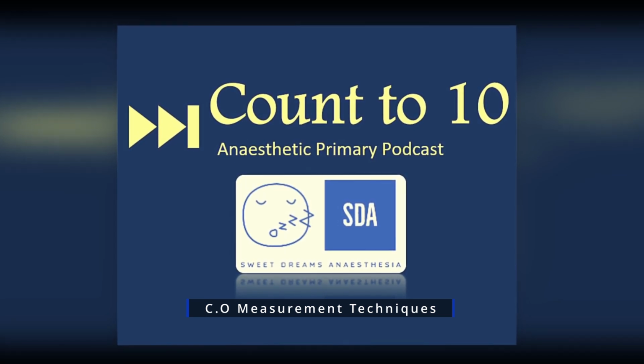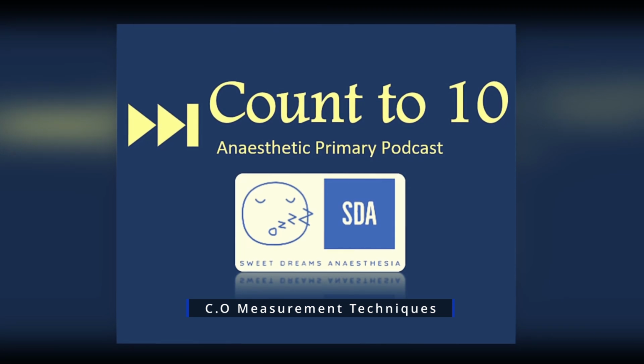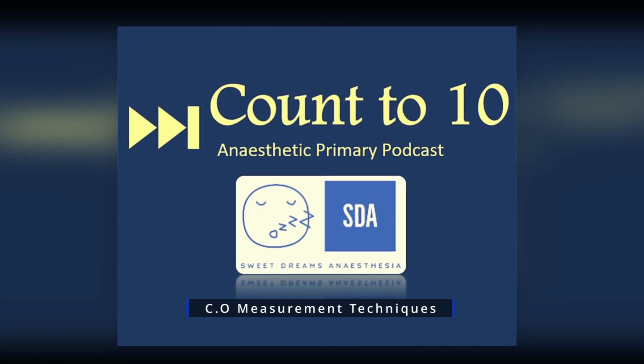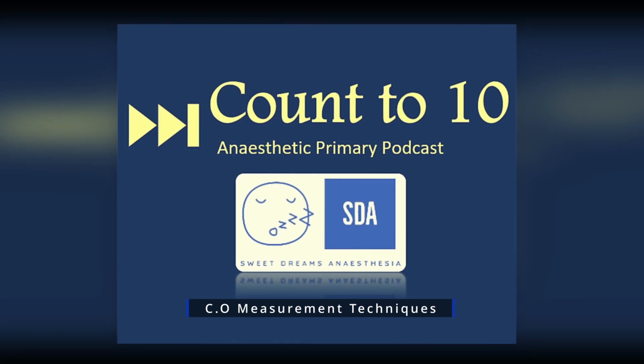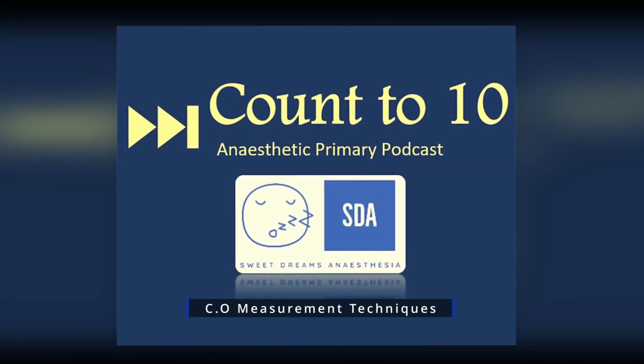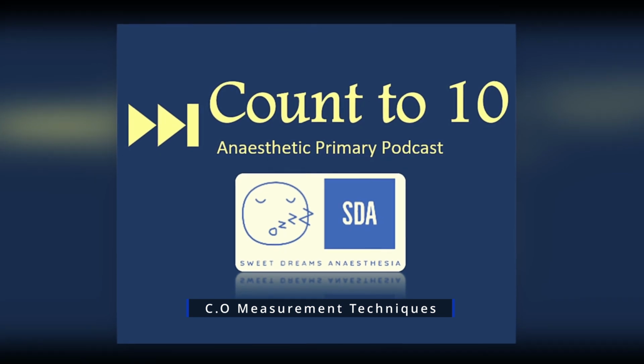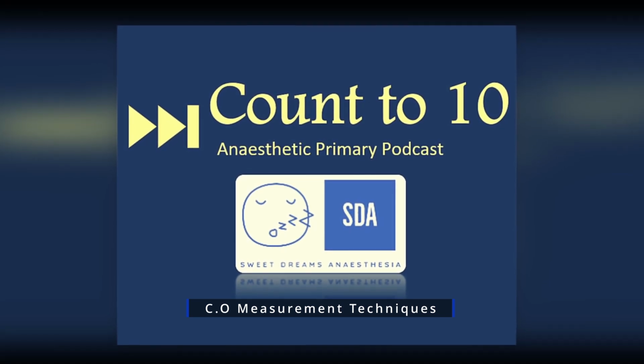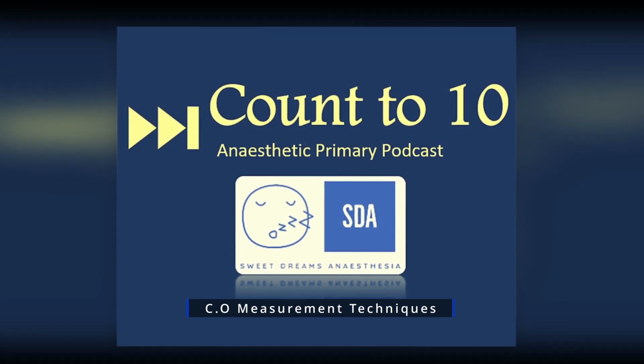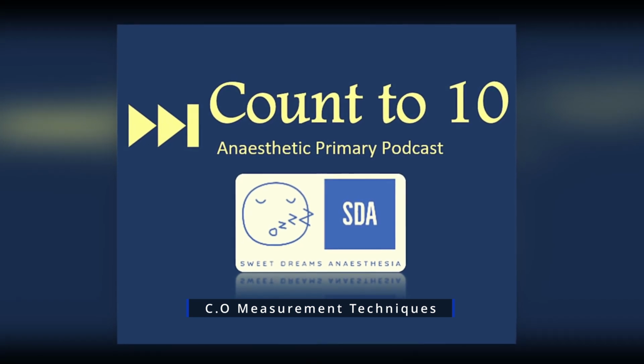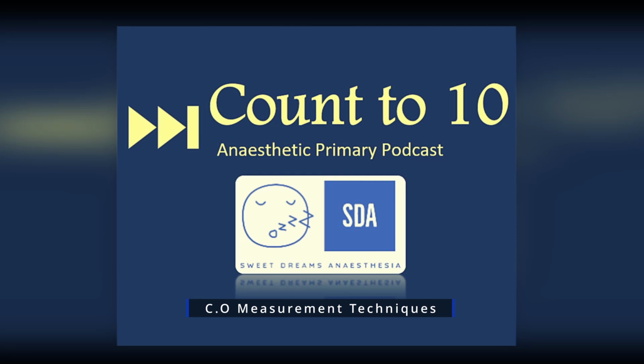Now these measurements are put into a complex equation called the Stewart-Hamilton equation, which describes this relationship and then spits out a cardiac output. The key thing with this technique is that you shouldn't just do it once. You should do this measurement 3 times and take the mean of these 3 values. This is because the thermodilution cardiac output measurement can vary by 10% from measurement to measurement.